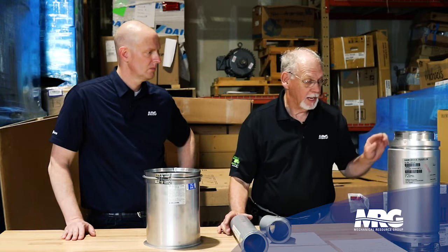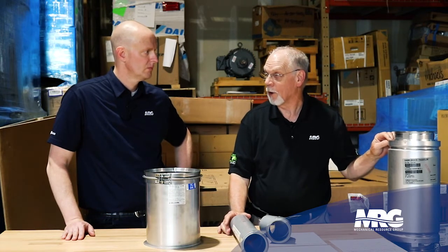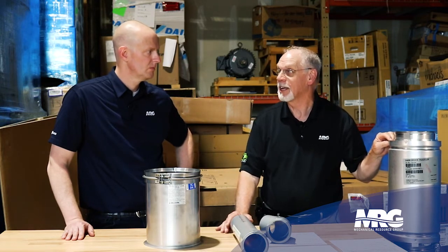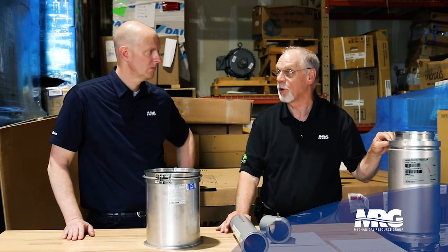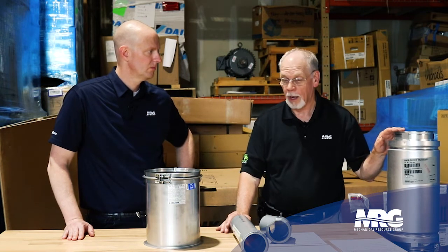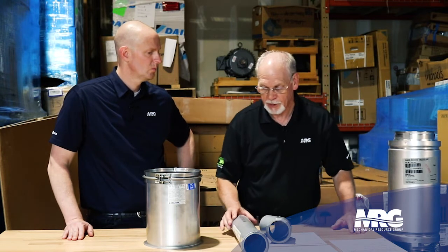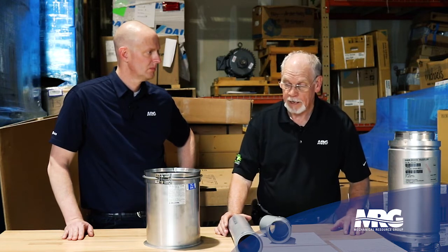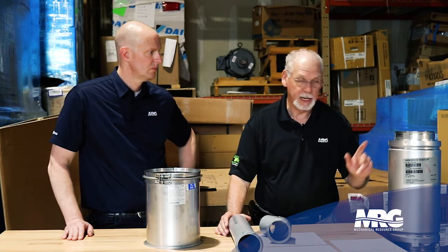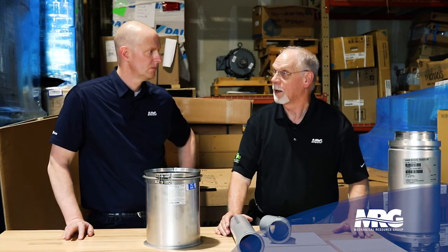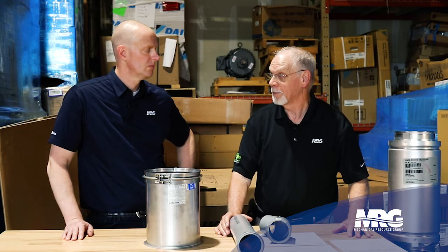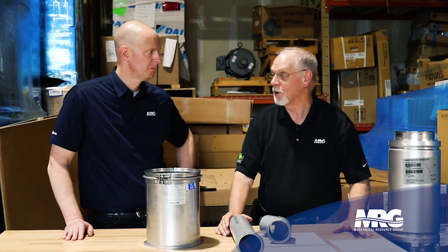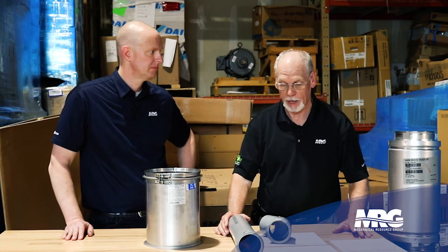They also have insulated duct on our vent piping, where you can get either 1, 2, or 3 inches of insulation inside, depending on the temperature of the flue gas. Because when we talk about flue gases, there's several things that we use that on. Of course, we have it on our boilers for our hot water. Where we've used it a lot with the insulation in it is on electric generators that are diesel powered. So it's an engine, so it's engine exhaust, and that gets hot. Right. And that's always double walled, and it's insulated usually on that, and that's for the protection.